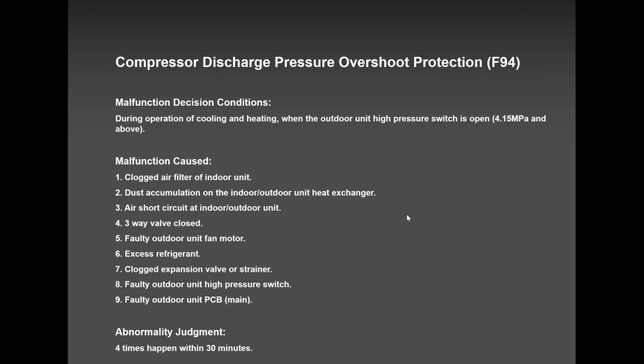F94, compressor discharge. Check if there are any filters that are clogged at the indoor unit. Check if the air circulation is not good. Too much refrigerant can cause this as well. And if everything is good, then the outdoor PCB is condemned here. And that is only if you keep getting F94, okay?